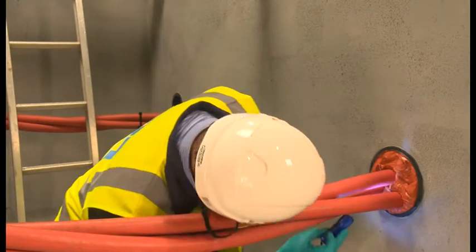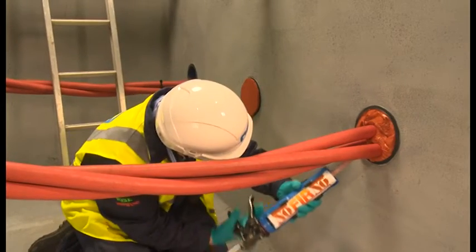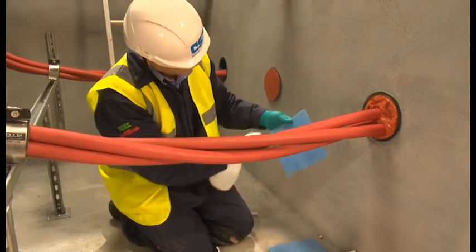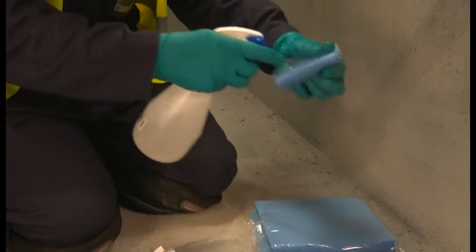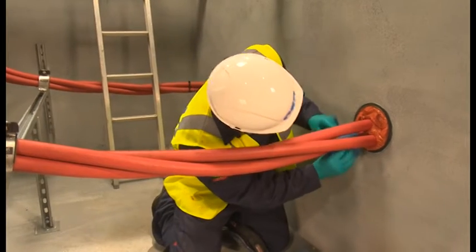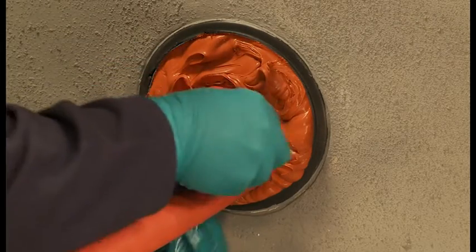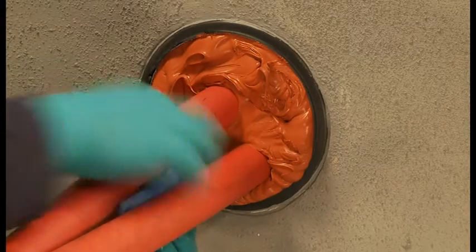Using a torch, check for gaps in the sealant and apply more sealant into any gaps if needed. Using the water spray, dampen the cellulose sponge. This is done to stop the sealant from sticking to the sponge whilst working with it. Using a dabbing motion, firmly pat down the Nofirno sealant, ensuring it makes good contact with both cable and the duct wall. Pay particular attention to the gaps between the cables to ensure good adhesion.